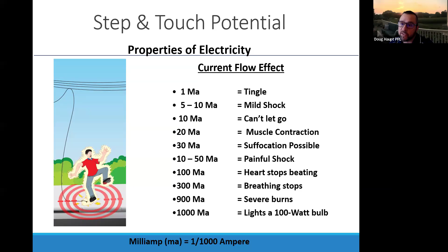Household current takes the lives of more people every year than our overhead distribution facilities do. So if you're going to do work in a home, simply walk down the steps, open it up, and shut the breaker off. I shut the main off, because somebody scribbled dining room next to that breaker, and did they scribble dining room next to the right breaker? All right, but use a tester, right? It's a $10 tester, stick the two little leads into the receptacle, make sure you got the right one, and shut the right breaker off before doing work on it. Small amount of electricity is all it takes to injure us or potentially kill us.